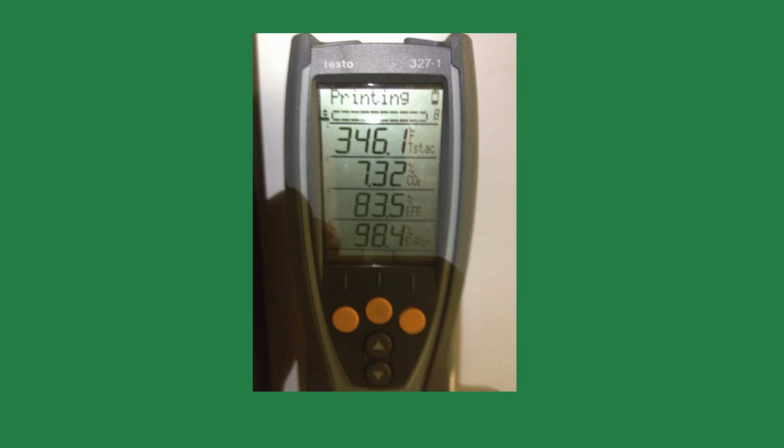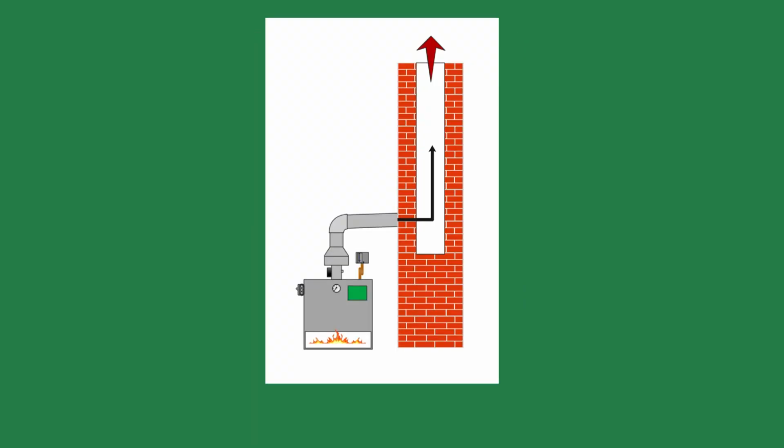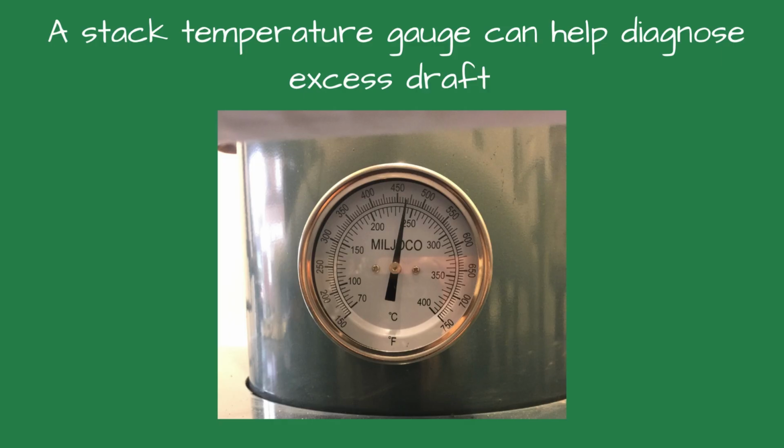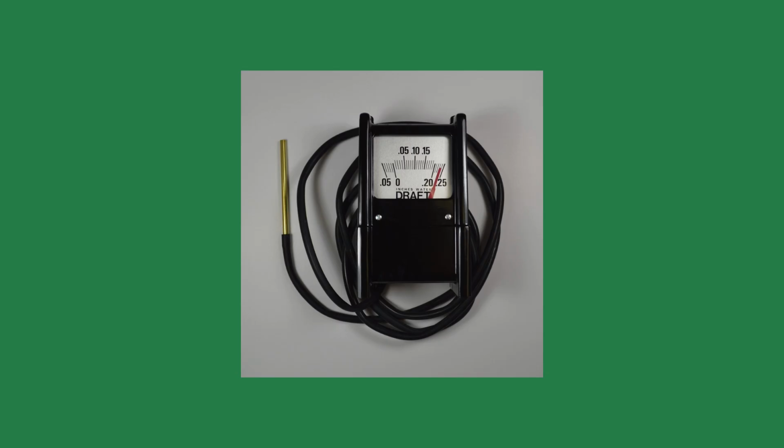If you live in an area with big seasonal temperature swings, consider adjusting combustion settings twice a year to compensate for draft variations. The draft is invisible, but its effects aren't. It impacts combustion, efficiency, burner performance, and even safety. Steam boilers are more sensitive because of the higher stack temperature and the potential for soot. So next time the system seems off, grab your draft gauge or manometer and pay attention to the flue. You might just save the boiler and your customer a lot of grief.